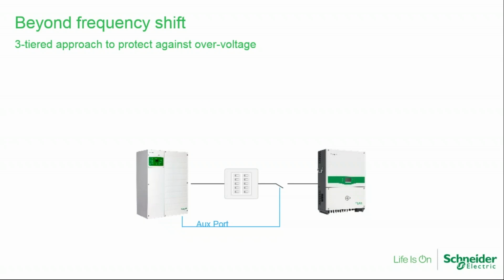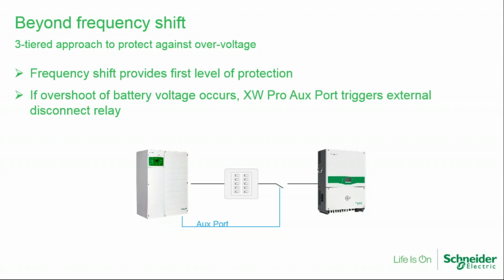So one of the things that we do to protect the batteries as well is we do the frequency shift, which is the anti-islanding. We do curtailment, which is having the PV inverter back off. And then we can use the XW Pro aux port to operate an external relay, which, if things get completely out of control, we can just disconnect the PV inverter physically. And that'll be based on the high battery cutoff setting.